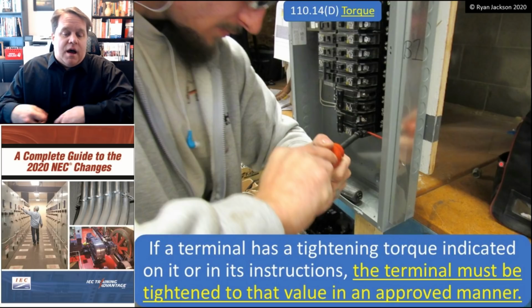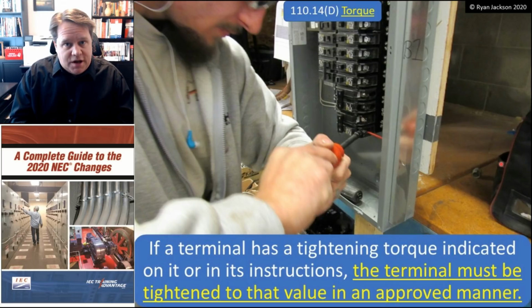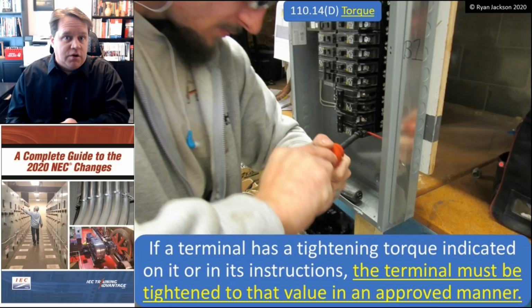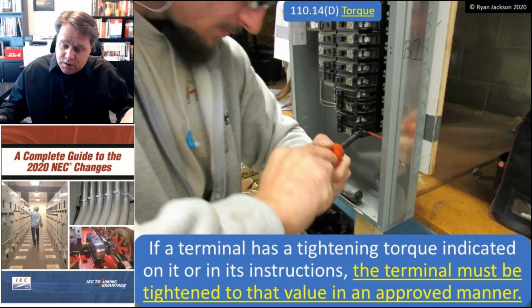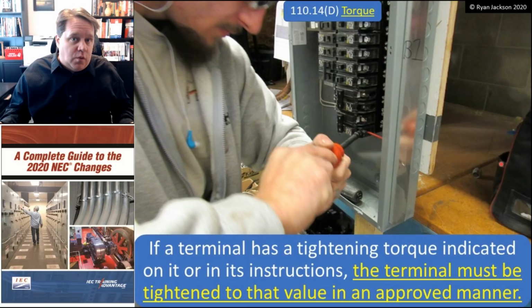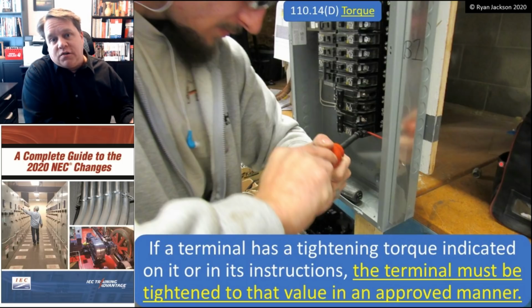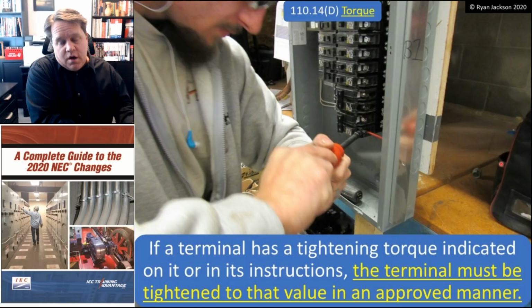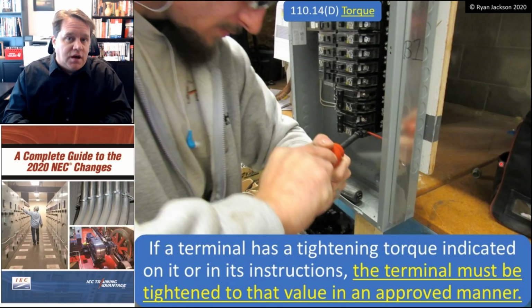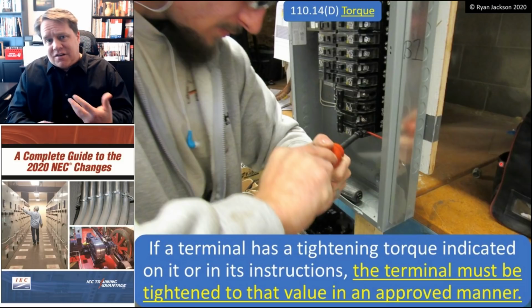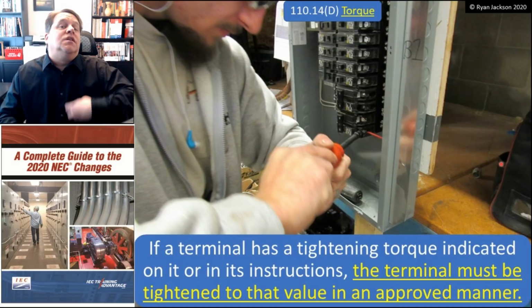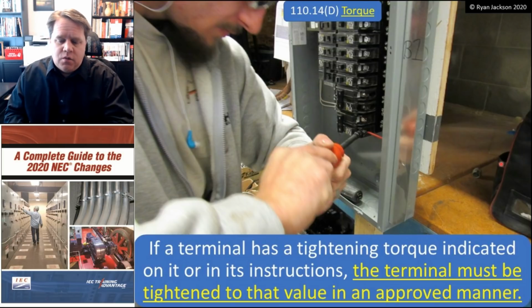Now, how were you tightening your terminations before the torquing was a requirement in this section? Well, to be honest, it's always been a requirement. We have to follow the manufacturer's instructions if we're using listed products, and the manufacturer's instructions told us to measure for tightness, to measure for torque. So this isn't exactly a new concept, but it's really being emphasized, and I'll tell you why. Kind of an interesting story.